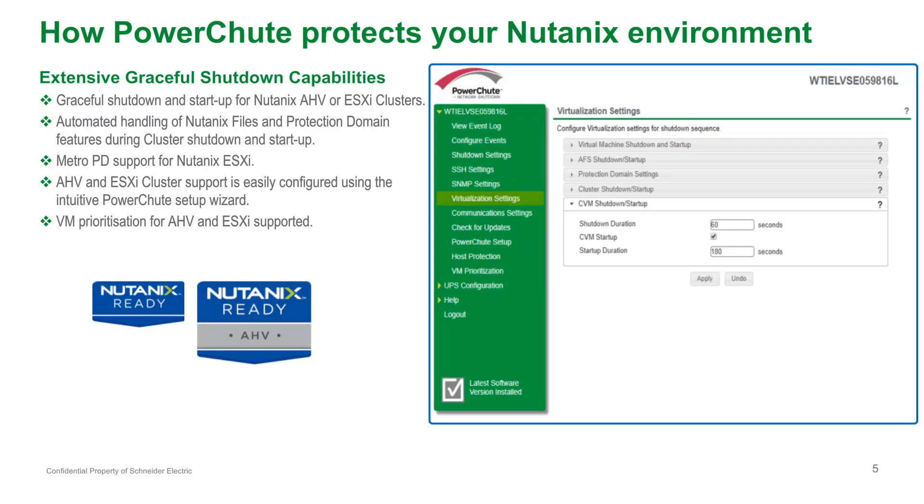PowerChute Network Shutdown is certified Nutanix ready for both the Acropolis hypervisor and ESXi. PowerChute provides the capability to safely shut down your Nutanix cluster when a power outage occurs. Additionally, PowerChute can restart cluster services and user VMs when power is restored. PowerChute issues commands to safely shut down the Nutanix Files cluster and bring it back up when power is restored. PowerChute will also detect any active replications that are in progress for a protection domain and cancel them.